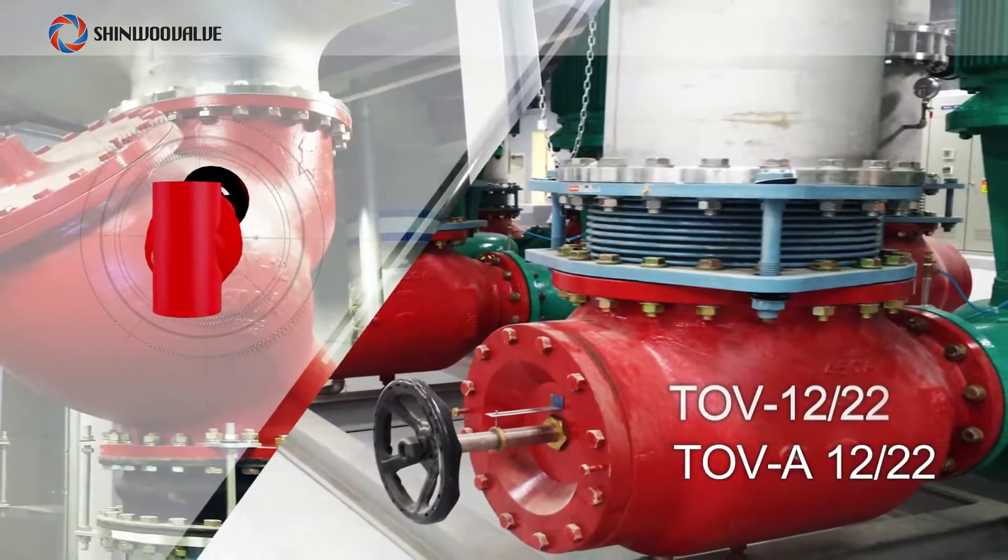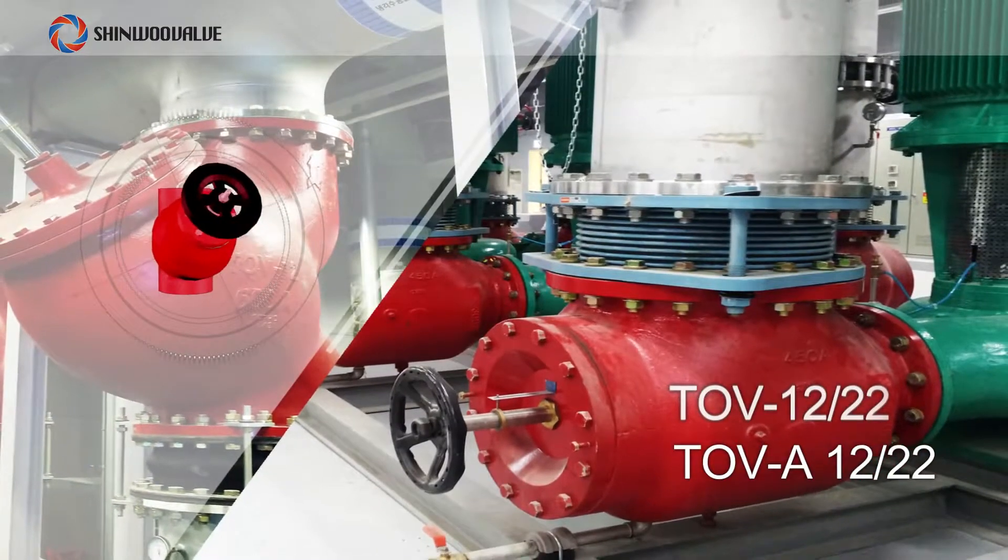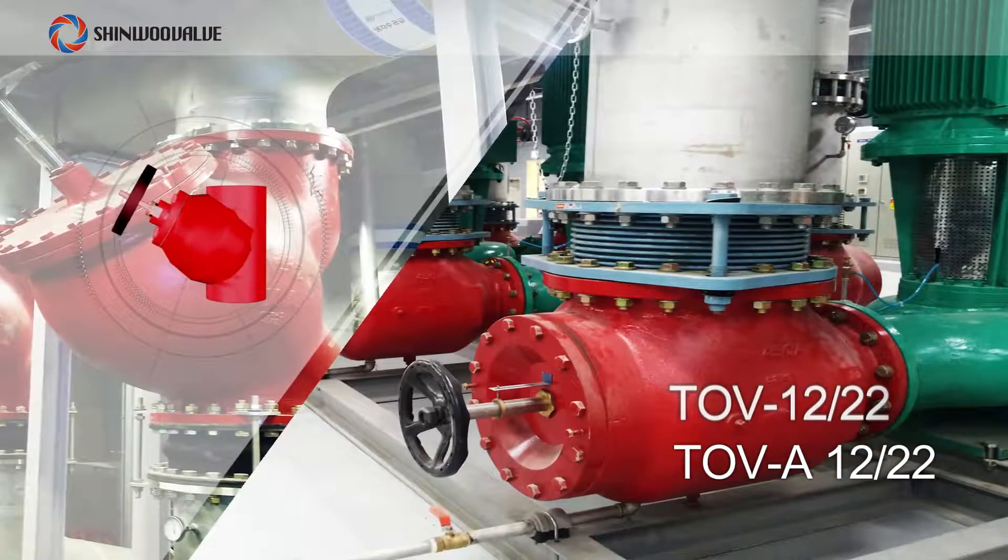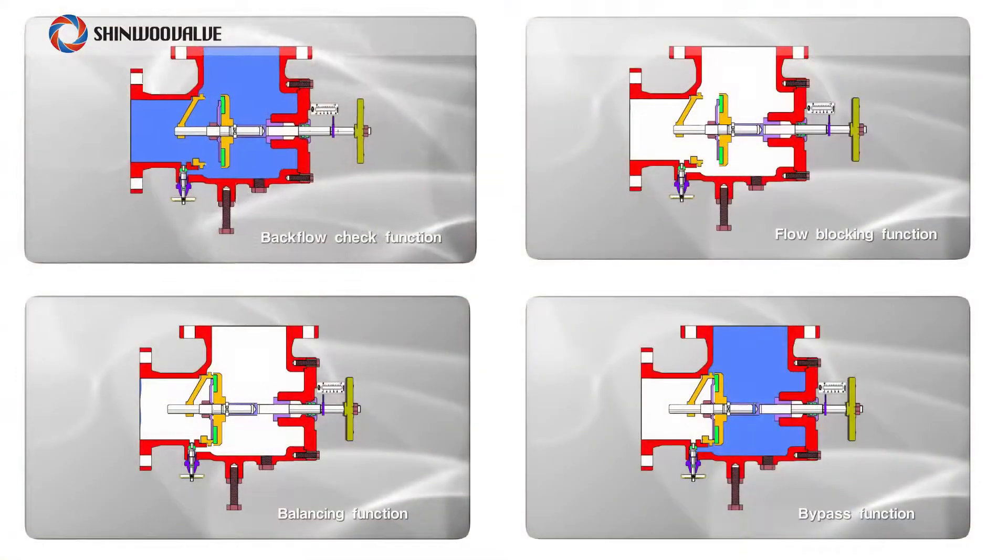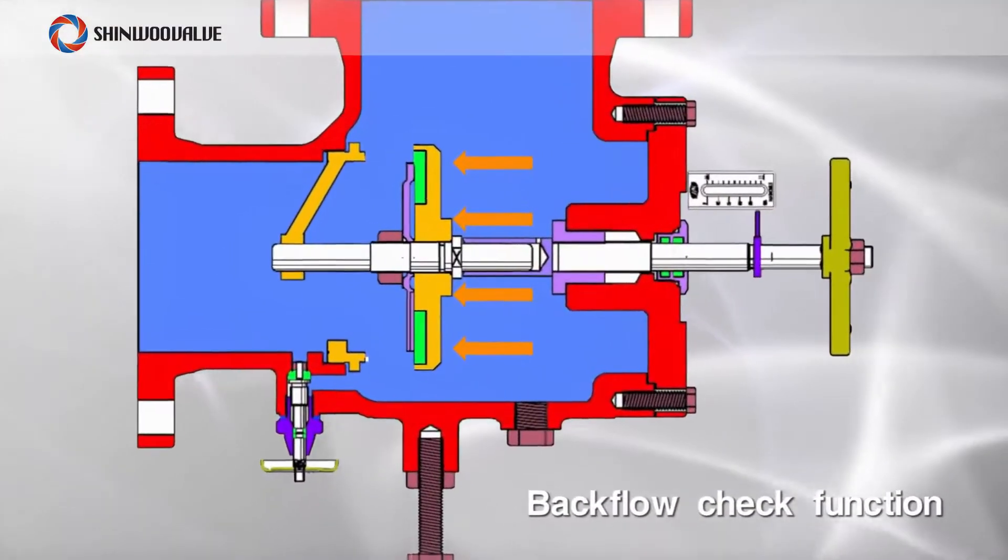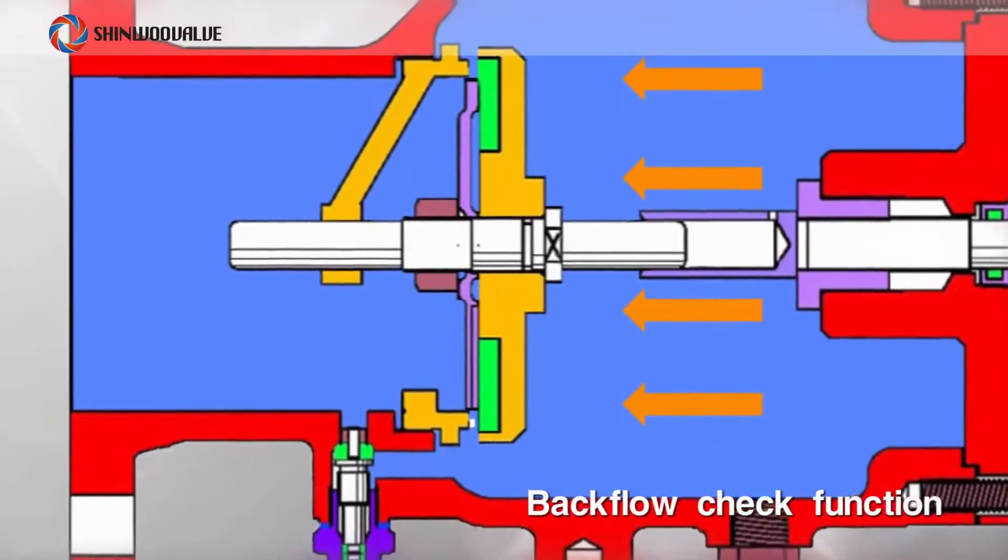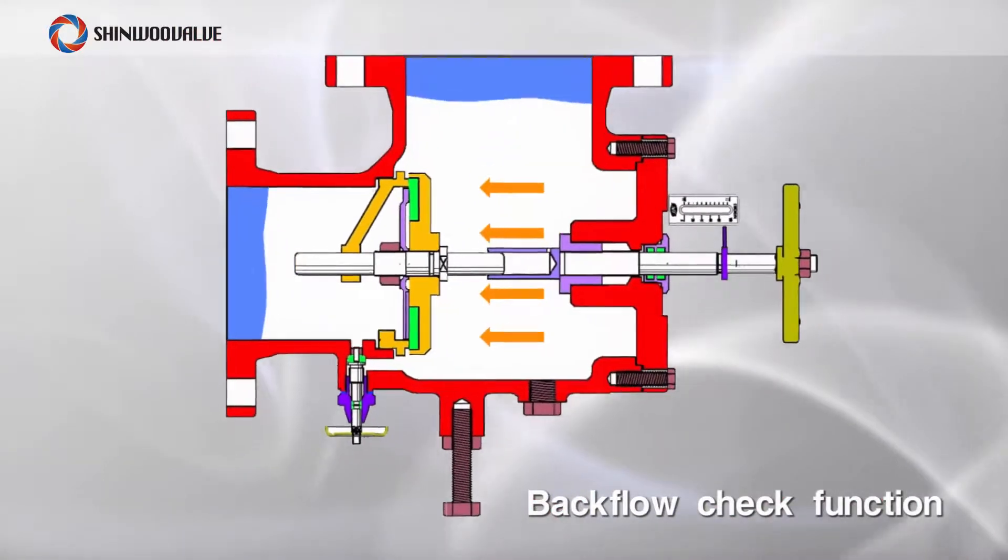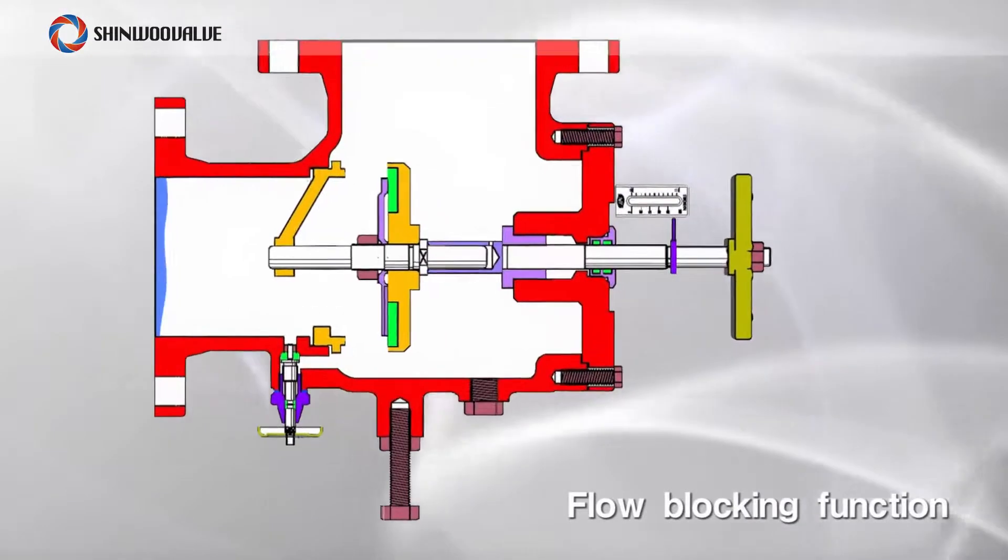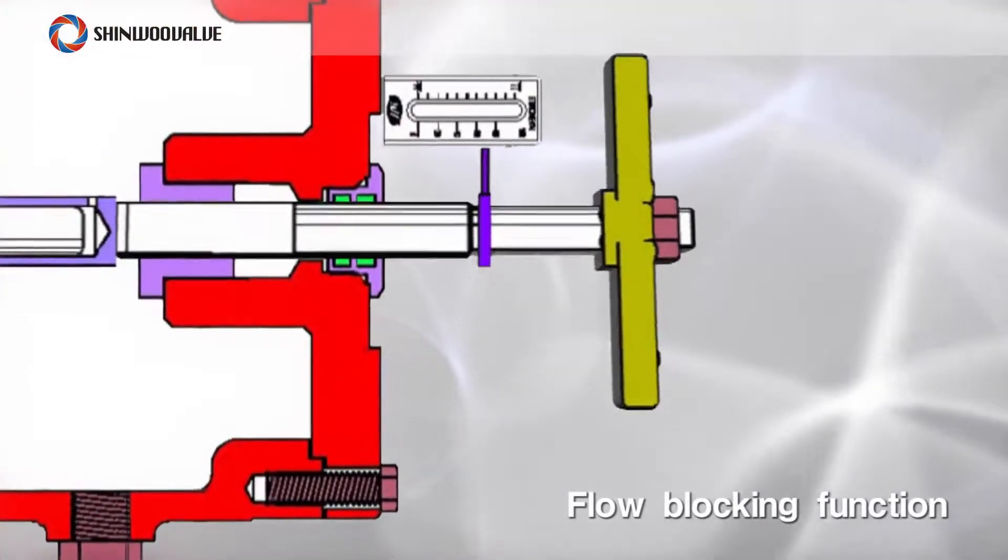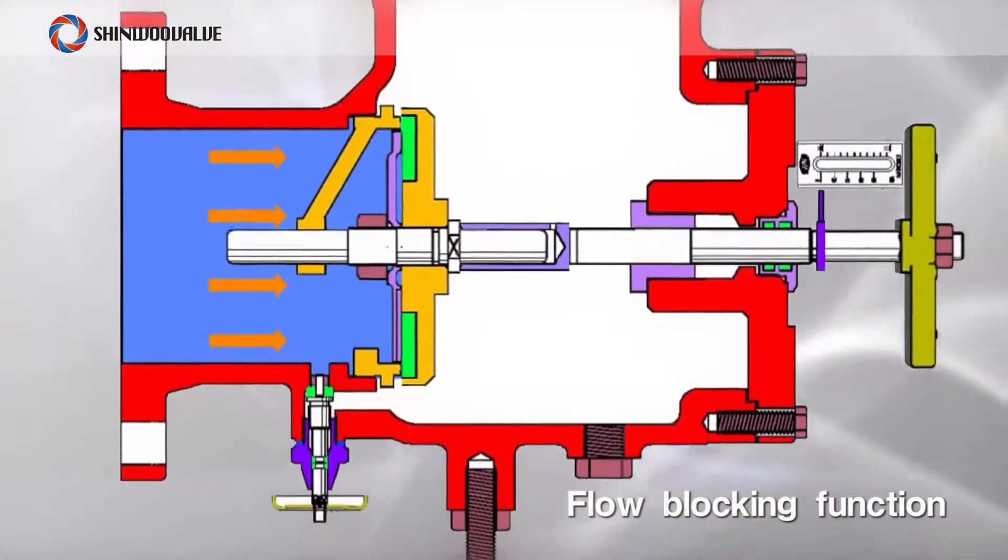A triple-duty check valve designed by Shinwoo Valve is installed at the outlet of the pump and prevents fluid from flowing backward when the pump stops its operation. Its backflow check function prevents the pump from water hammering when it abruptly stops and with its flow blocking function it is possible to block fluid flow inside the pipe by closing the valve with the handle.